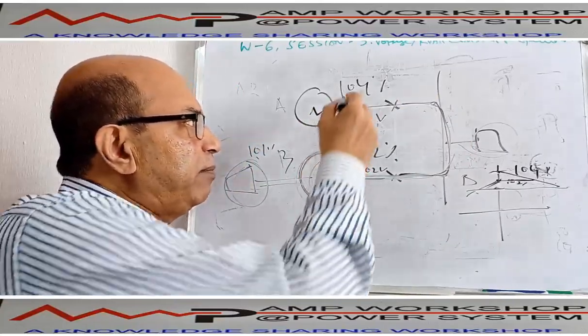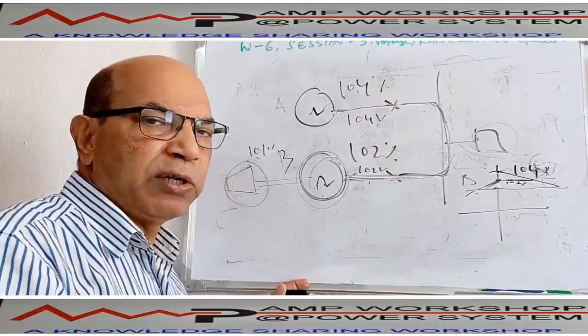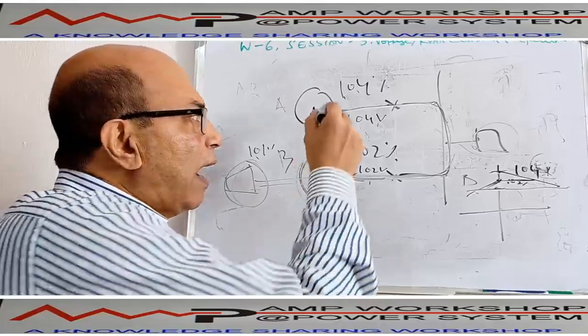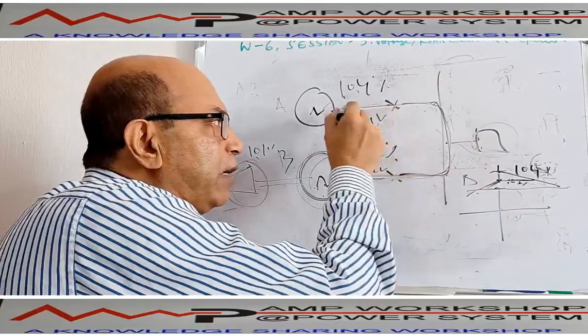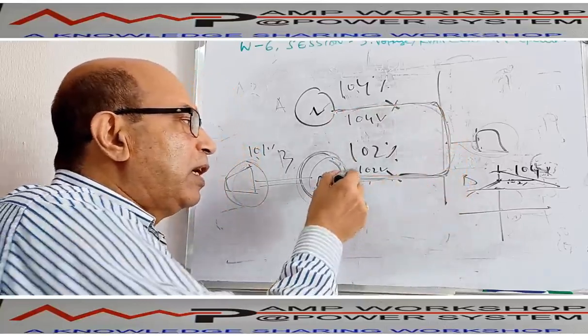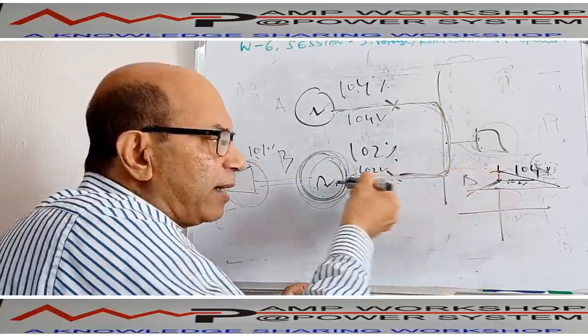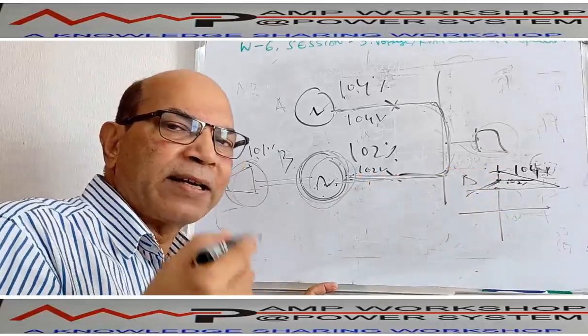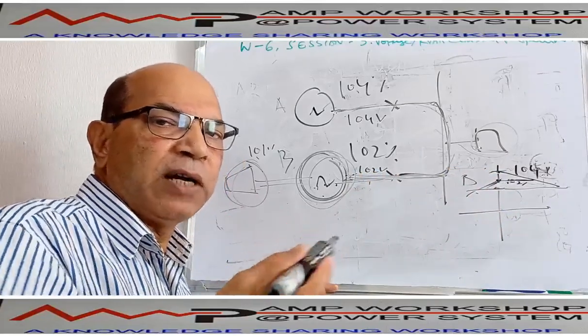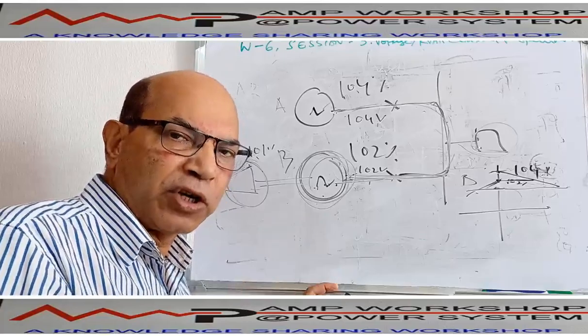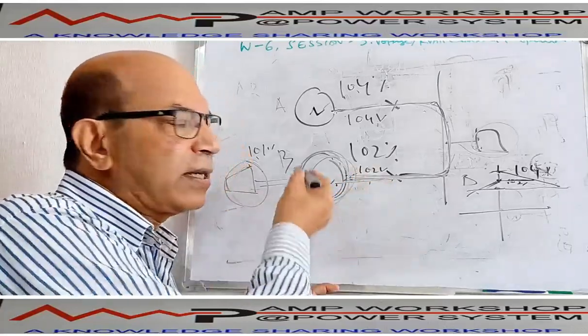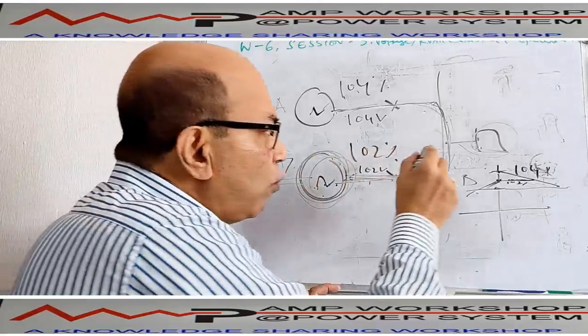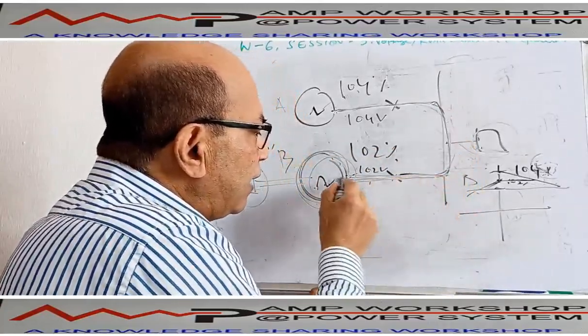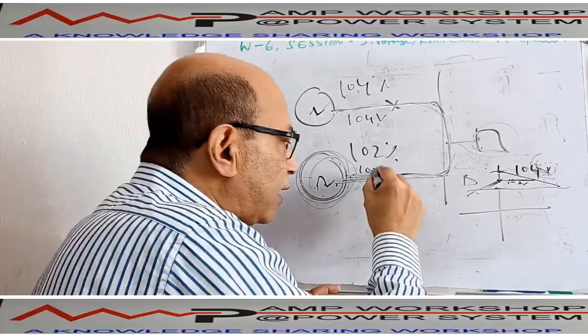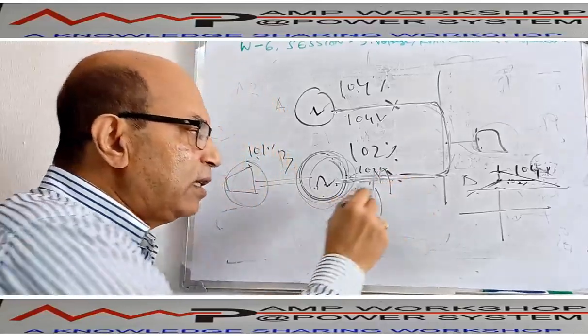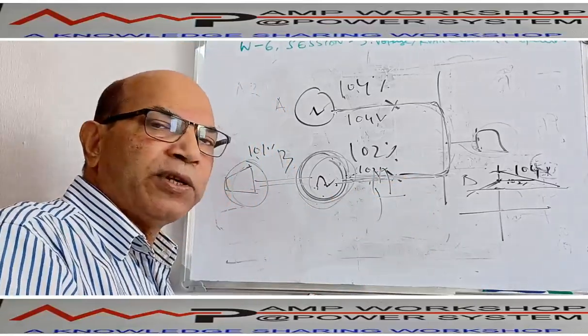Same as with active power, if these two machines have different speed droop, then the higher speed machine will take all the active power, and active power will flow from this machine to this machine. Then this machine will be absorbing active power from the system, so the machine will be acting as a motor. That's why we give the reverse power flow protection. That's why we have to sense whether the current is going to the machine or not. That means from the generator terminal we have to put a CT. This CT we call a cross current compensation CT.